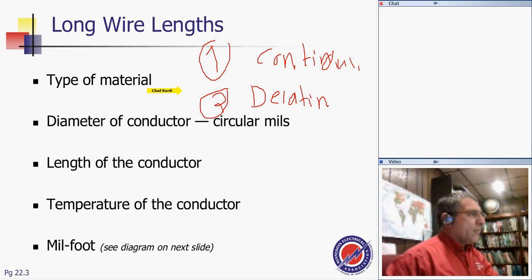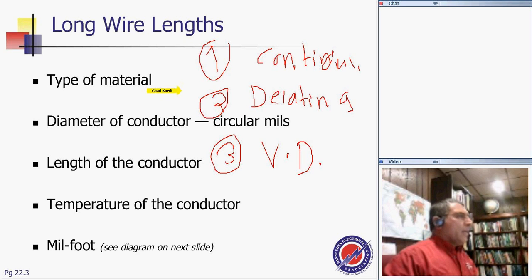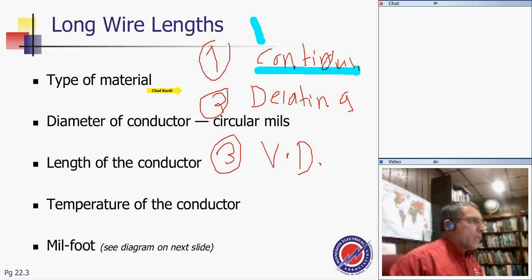Okay, derating. Number three, my friend, is based on voltage. Makes sense, huh? So what we do, guys, is when we size a conductor, you have to take into consideration the following. Number one, is the load continuous? If it's continuous, you have to multiply by 1.25, right? That's how we size continuous loads. That's one.